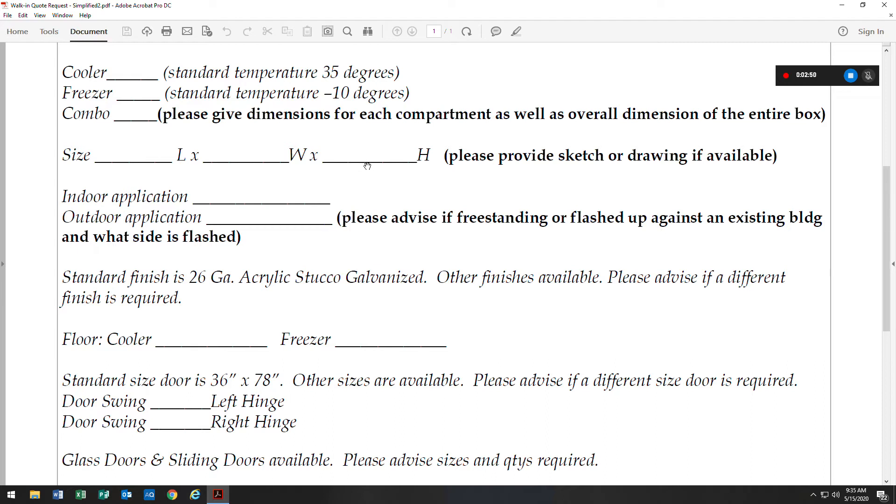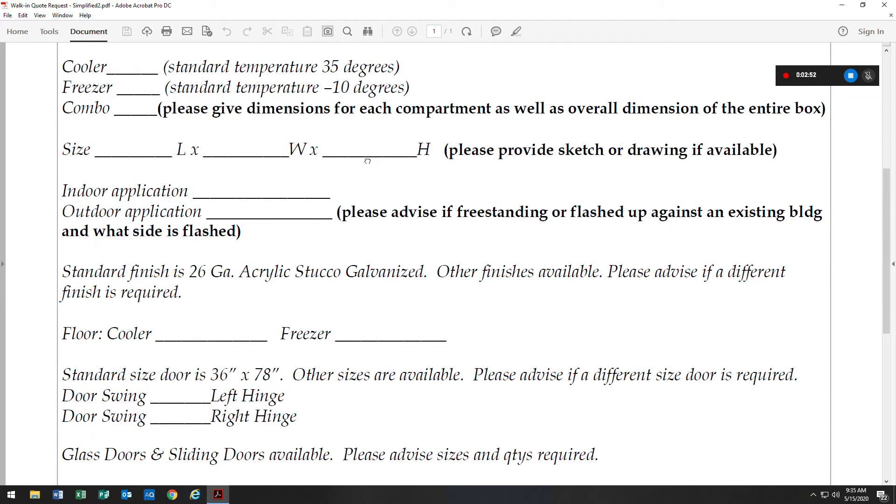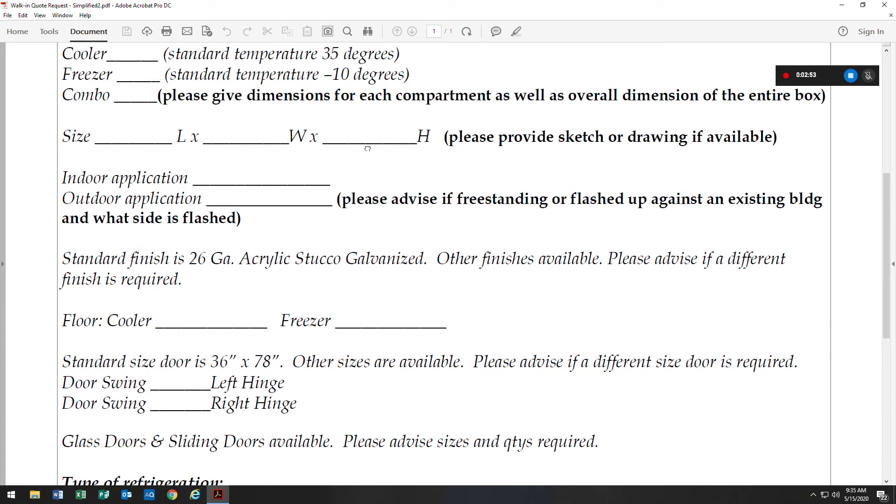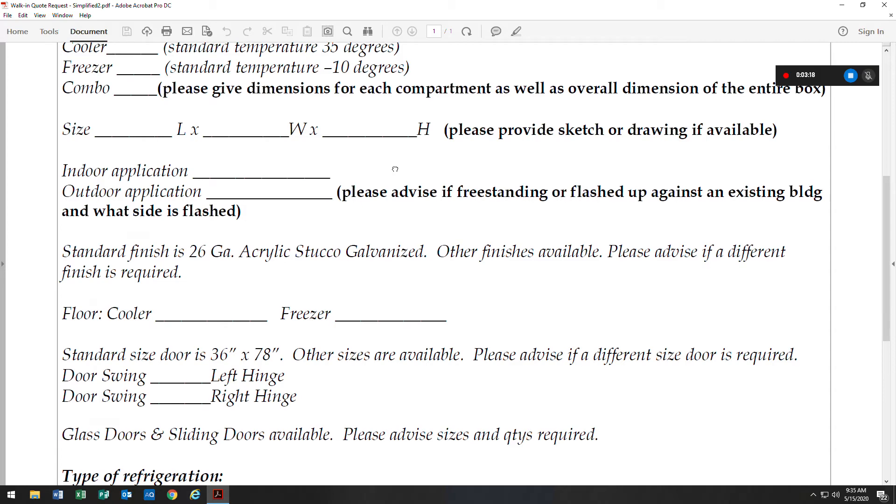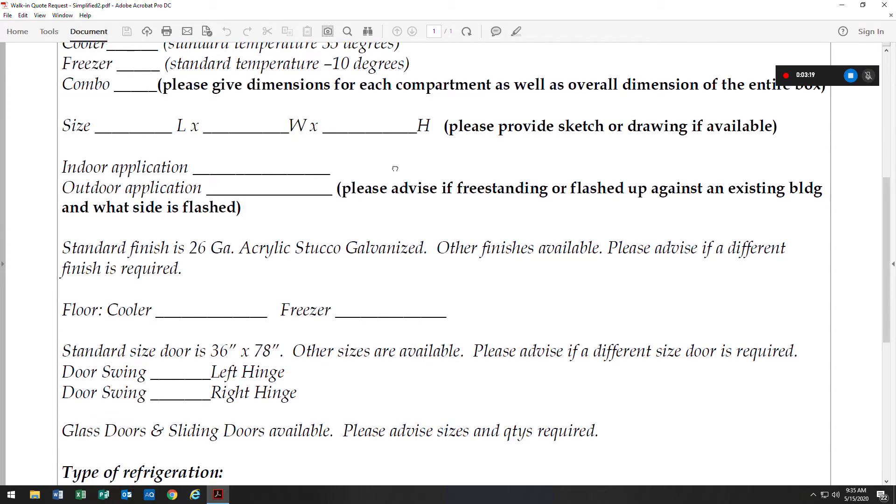Our standard heights with floors are 7'6 and 8'6, without floors they're 7'2 and 8'2. On freezers, it's 99.9% of the time we will include a floor in the freezer. There are special exceptions, but that discussion would need to be had with either your Master-Bilt representative or myself when the quote request is being asked for.